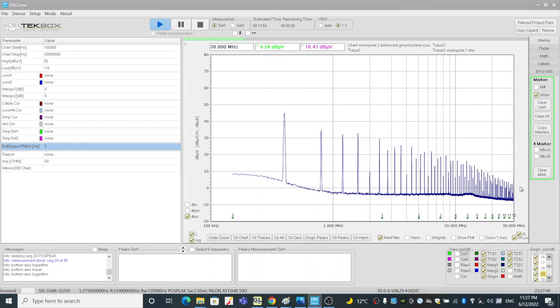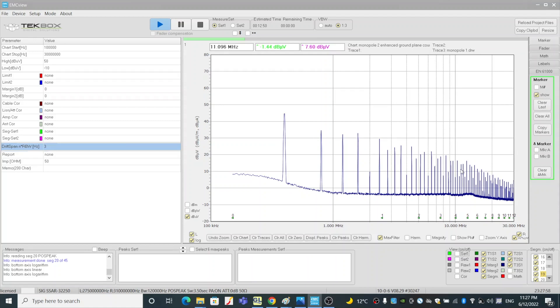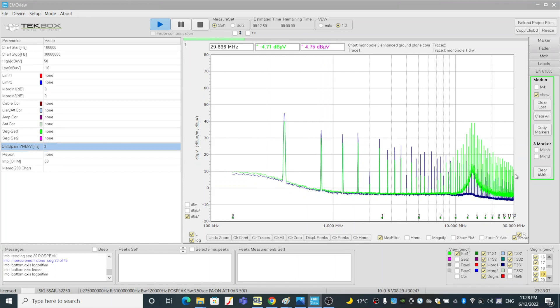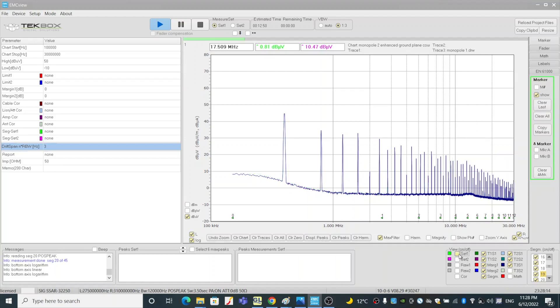The reason for that is this is the result that we didn't use really good bonding, just to give you the comparison results. As you can see, when you have really good bonding between the counterpoise and the ground plane, you actually collect more common mode noise, hence showing here. Whereas if you have bad connection, as shown in this case, you won't collect enough common mode current. Therefore the results are not valid.